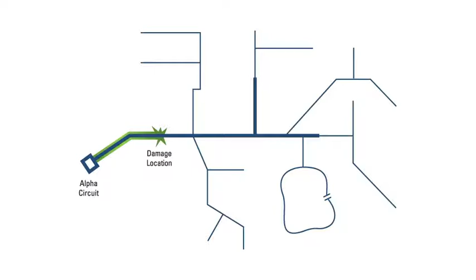At the damaged location, the assessor records observations of the damage: poles that are broken or leaning, and size and class of poles if known; transformers that are damaged or need replacement, including size and type if known; wires down, including voltage, primary, secondary, or service, size and type if known; and any other major damage to capacitors, regulators, anchors, reclosers, cutouts, or framing.